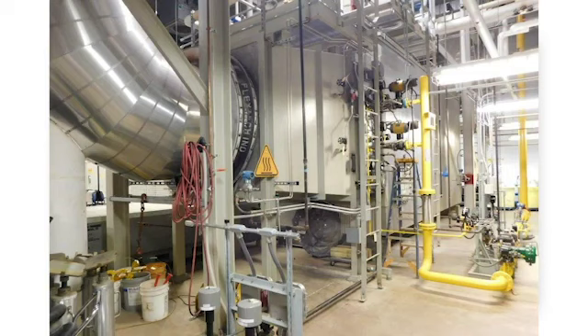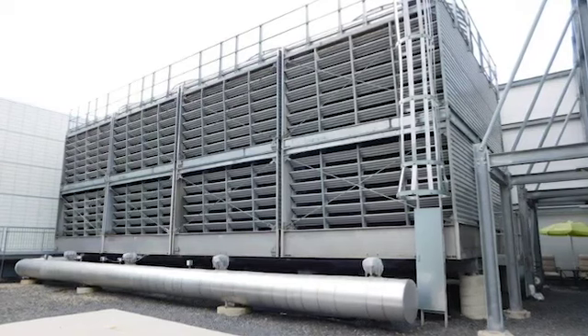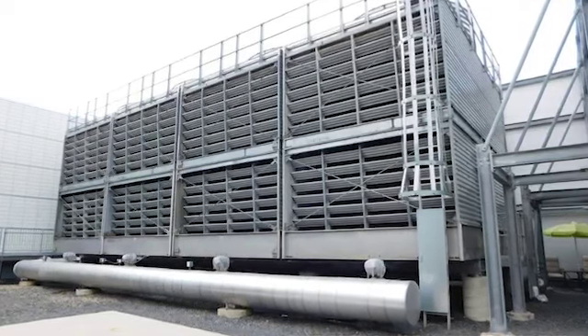And so regardless of the output of the turbine, we're able to bring that duct burner in and make very efficient steam. Okay, and that's really good for the customer, regardless of the market conditions. Sometimes the electric market is extremely competitive, and sometimes it's very soft. But regardless, we're still getting value by using this duct burner to take care of the steam needs of the facility. We'll take you quickly outside to the cooling towers.